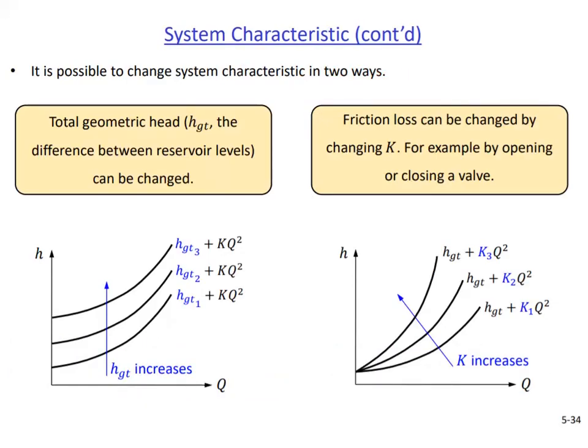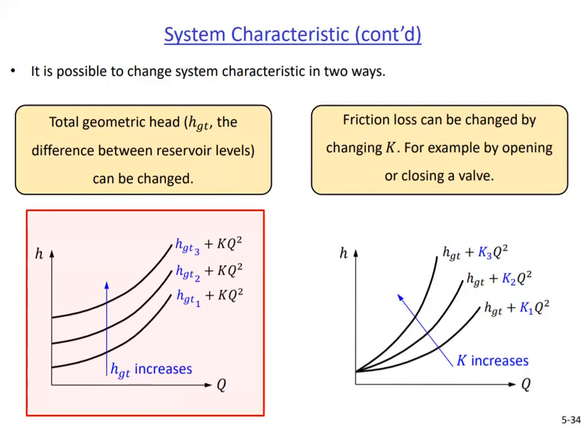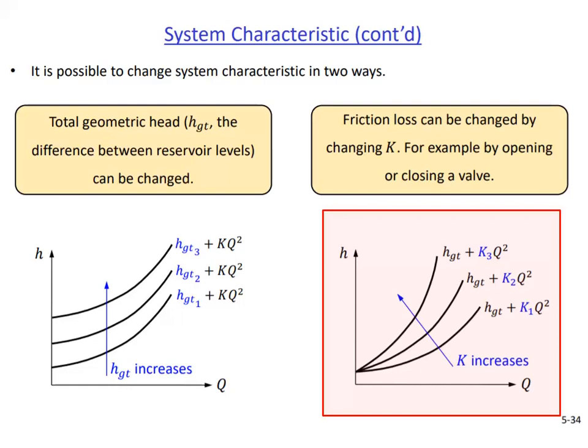For the simple two-reservoir system that we are studying, the system characteristic curve can change in two ways. If the total geometric head changes, for example by changing the elevations of the reservoirs or by changing the liquid levels in them, the system curve shifts up or down. If the K parameter changes, for example by opening or closing a valve in the system, or by redesigning the routing of the pipes, or by changing the pipe diameters used in the system, or by any other means that affect the losses, the slope of the system curve changes.